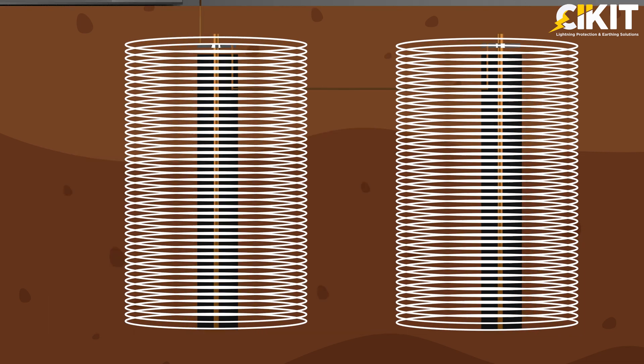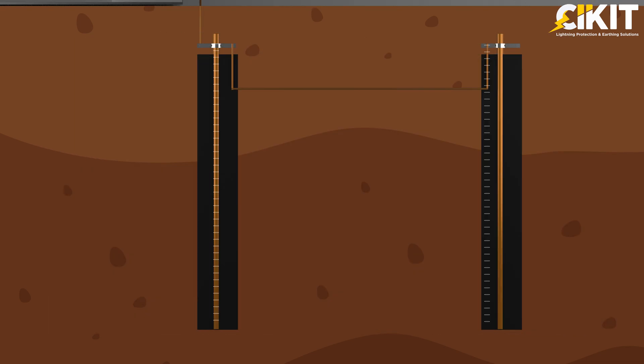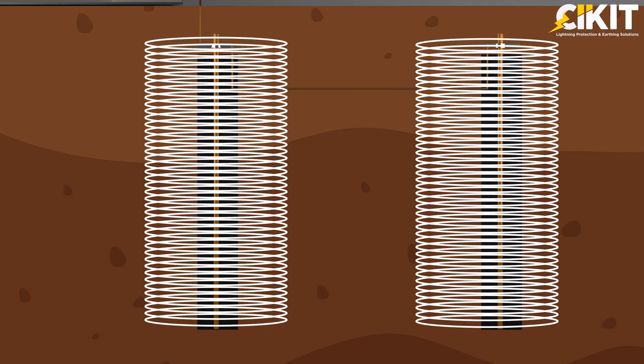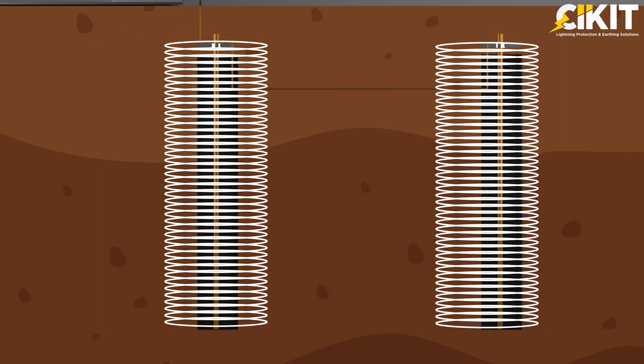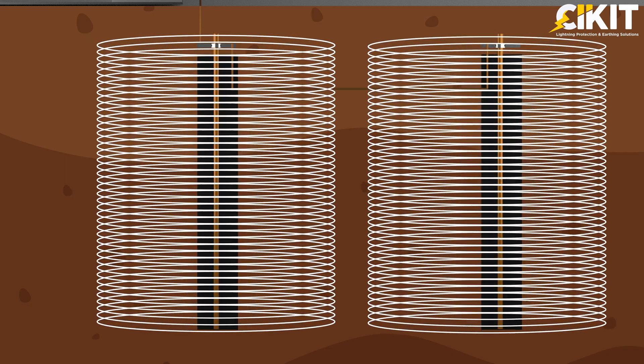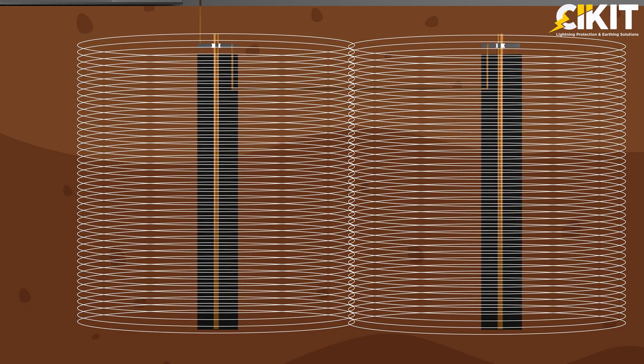Hence, considering the effects of spacing in deciding the combined resistance value, it is always advisable to maintain the distance between the earth electrodes as twice or equal to the length of the earth electrode.